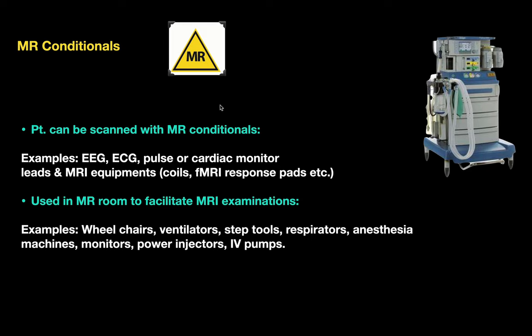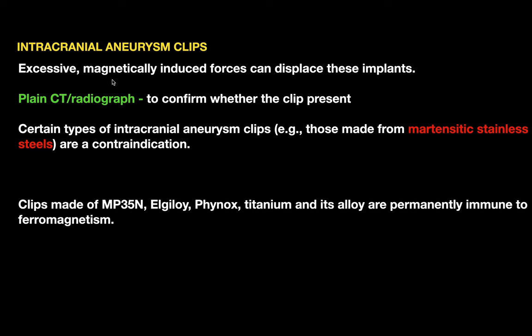MR Conditional equipment used in the MR room to facilitate examinations includes wheelchairs, ventilators, step stools, respirators, anesthesia machines, monitors, power injectors, and IV pumps. Intracranial aneurysmal clips are also MR Conditional. Excessive magnetically induced forces can displace these implants, so plain CT or radiograph should be performed to confirm whether a clip is present. Certain types of aneurysmal clips made from martensitic stainless steel are contraindicated; clips made of MP35N alloy, Elgiloy, Phynox, titanium and its alloys are permanently immune to ferromagnetism.